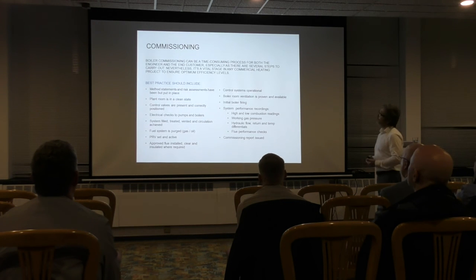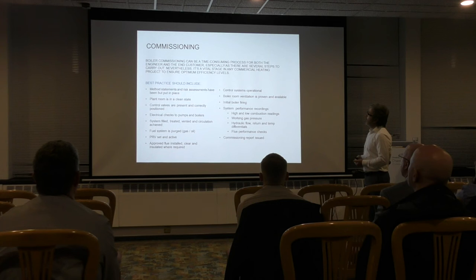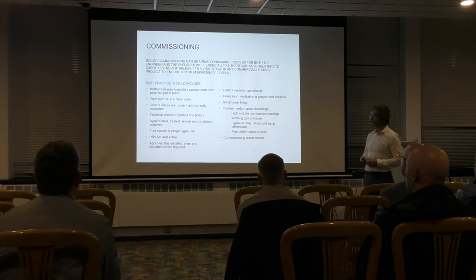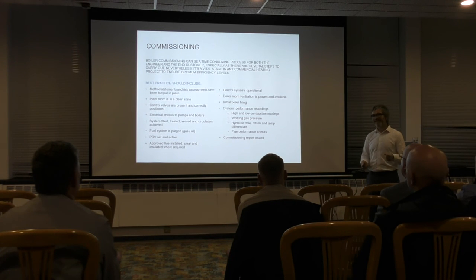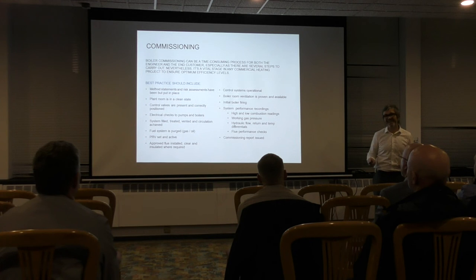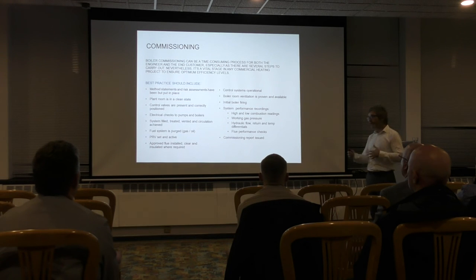And finally, looking at commissioning. I suppose us, along with every other boiler manufacturer, whoever requests commissioning from us, be it contractor or whatever, we will then send them a tick sheet essentially. That tick sheet is a requirement of what we would expect them to do prior to us going to site to commission the boilers. It safeguards both of us.